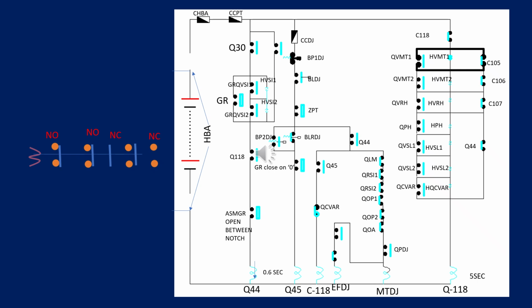Now what will happen? First, when you have closed the battery switch, immediately you see Q45 will be energized. How? Through this CCDJ. BP1 DJ is a spring switch, for tripping the DJ. It is normally in closed condition. It is a normally closed contact switch, so it will be in closed condition.